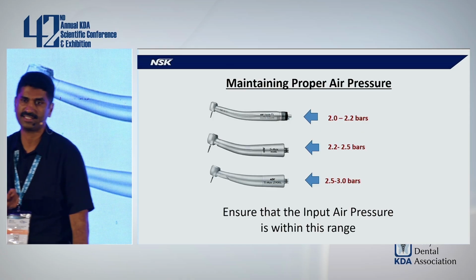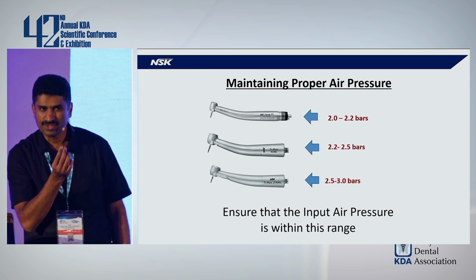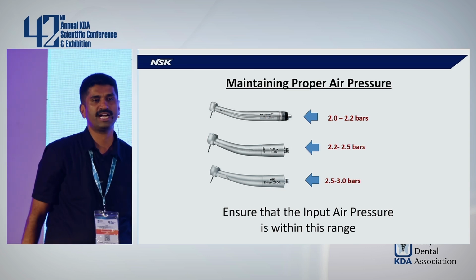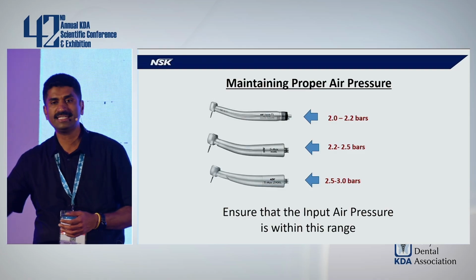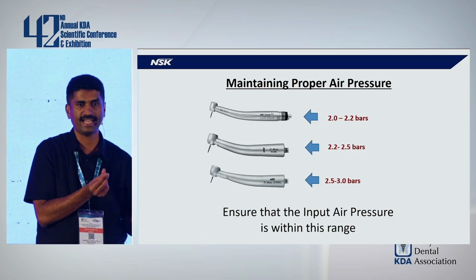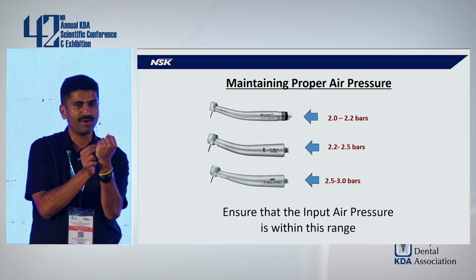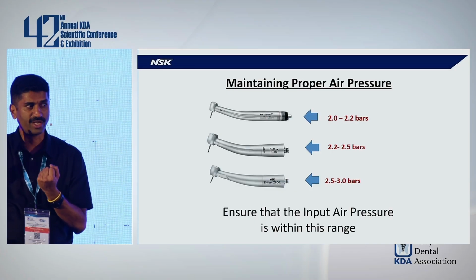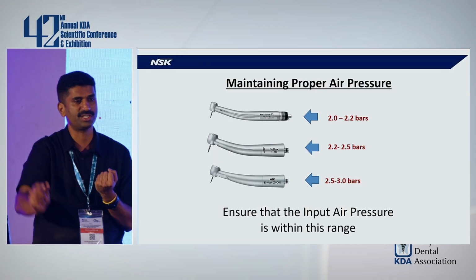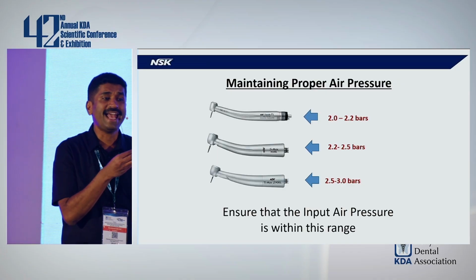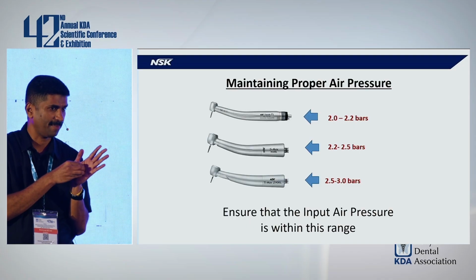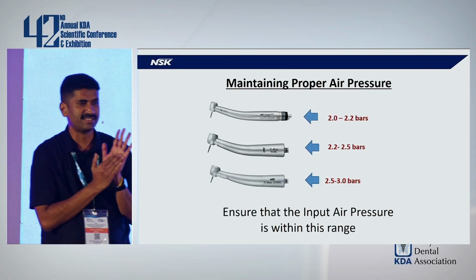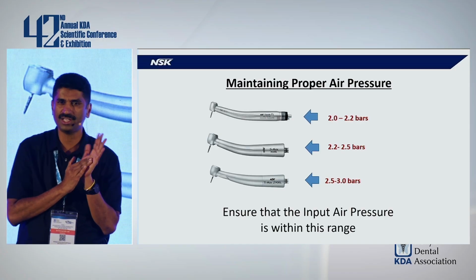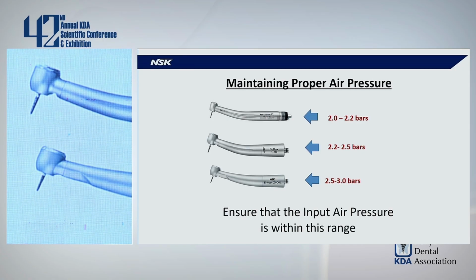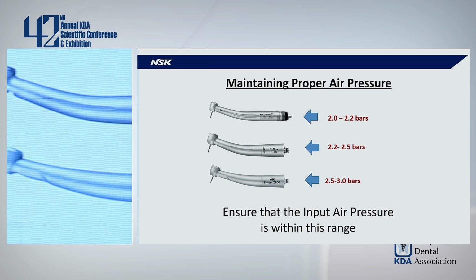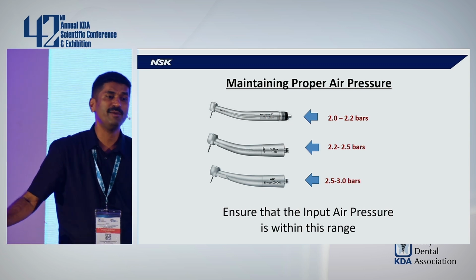Now, how to get this checked? You can do a simple test before you start your operation. Just take the tubing from the dental chair. No need to install the handpiece. Take a white tissue paper, cover the tubing, close the water knob. Do not switch on the water, just close the water knob, and press the foot control. Only air should come into the tissue paper. If you see that your tissue paper is wet, or if you see some yellowish, orangish or blackish particles coming into the tissue paper, that means the air coming from the compressor is not clean. So there are some impurities there.